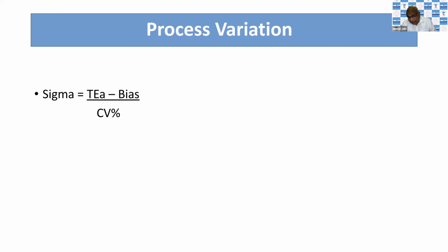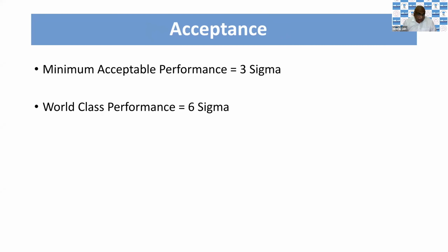Otherwise, in our EQAS, we are taking care of only accuracy, and in our IQC, we are taking care of only our imprecision. Here, we are integrating both. So this is good way of checking a quality of a particular analyte.